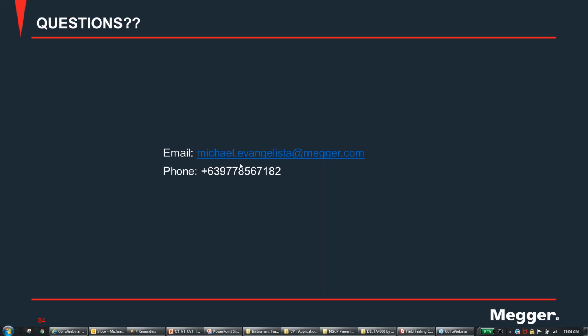In VTs, connecting load burden actually reduces the ohmic burden. So what is the limit for loading VTs? The burden is what was indicated in the nameplate. But if you are referring to the PS core again, then I don't know why they don't have an indication of the burden. So I guess what we need to ask here is the manufacturer of those PS CTs or VTs.